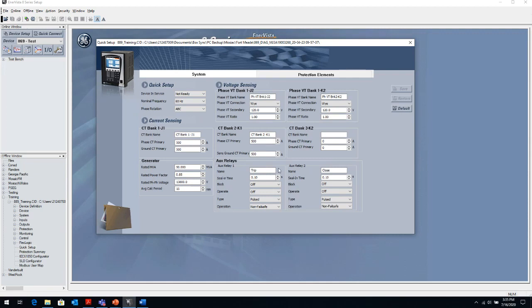And then you will select, relay 1 by default in the 8 Series is the tripping relay. So that's why we usually name it the tripping relay. And I recommend you keep that the way it is. So don't change the functionality of relay 1 or relay 2. Leave those as default, which is the trip and close relay. And I'll explain why when we go to the protection element setup.